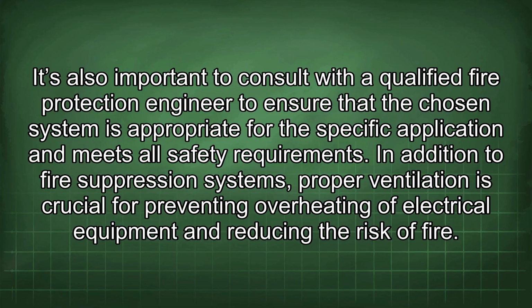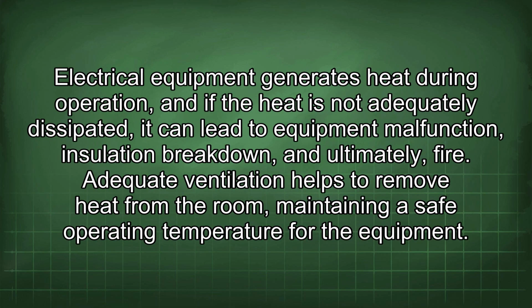In addition to fire suppression systems, proper ventilation is crucial for preventing overheating of electrical equipment and reducing the risk of fire. Electrical equipment generates heat during operation, and if the heat is not adequately dissipated, it can lead to equipment malfunction, insulation breakdown, and ultimately, fire. Adequate ventilation helps to remove heat from the room, maintaining a safe operating temperature for the equipment.